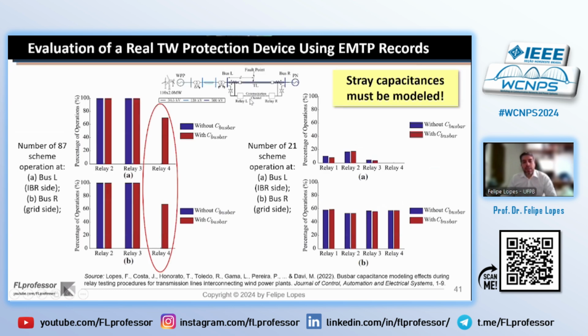The final result is basically an experience that we had testing real devices, and it motivated us to propose a recommendation for modeling this type of system when you are interested in testing real traveling wave protections. For instance, by modeling a typical topology like that one without the busbar capacitance and with the busbar capacitance, the traveling wave differential protection did not operate when we did not model the busbar capacitance. But we know that this busbar capacitance exists.